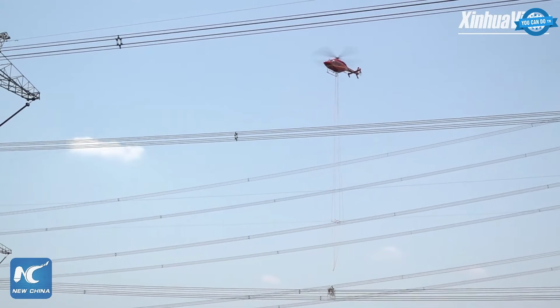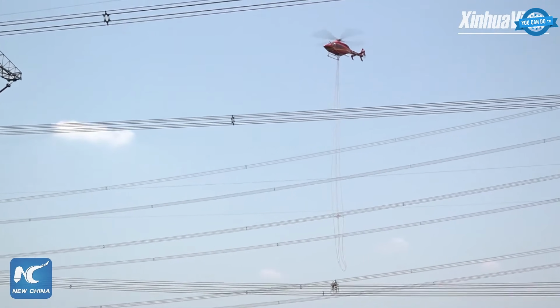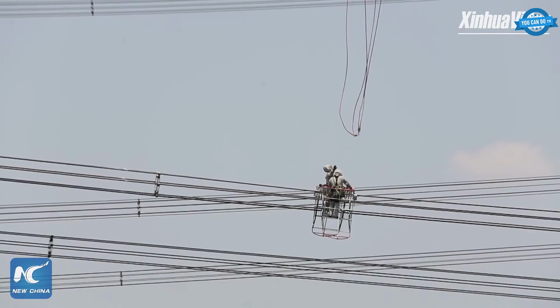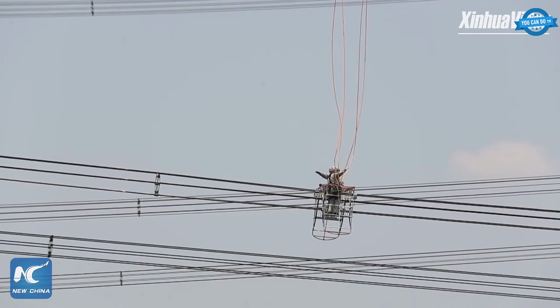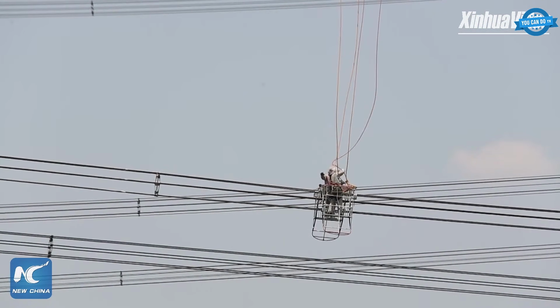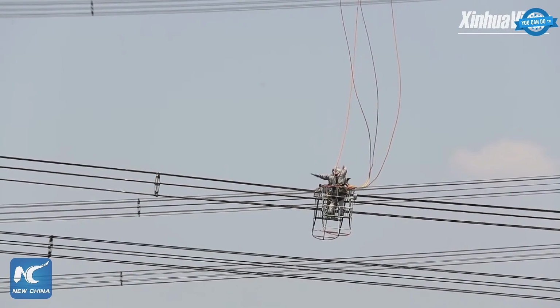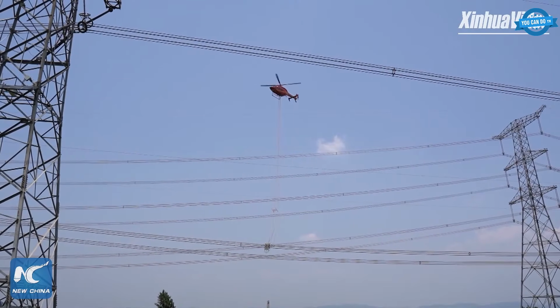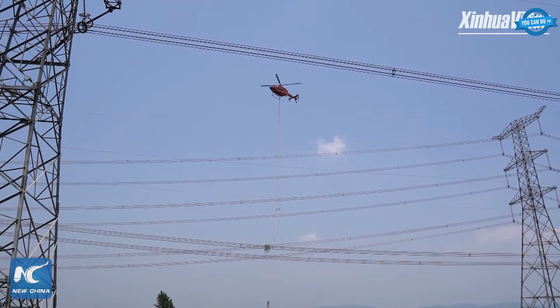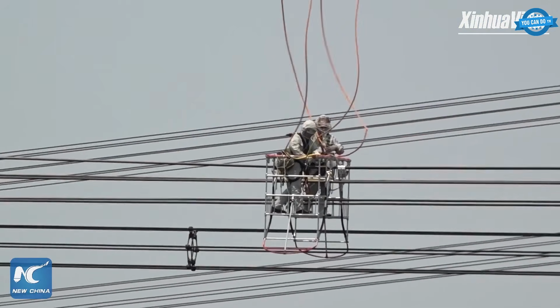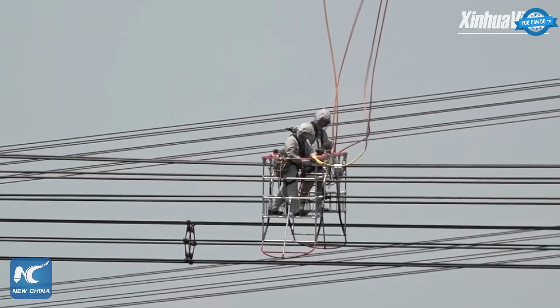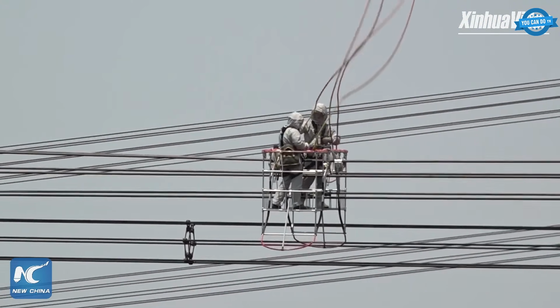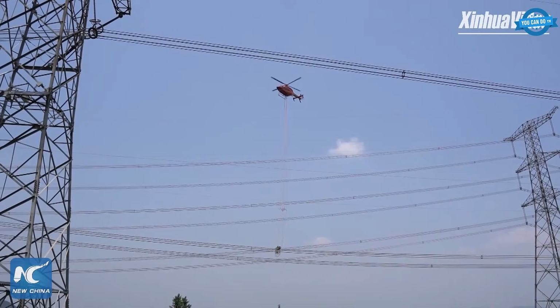Live-line helicopter maintenance is how damaged spacer bars get replaced without dropping the line. Linemen ride in a basket suspended 40 meters below the helicopter on insulating rope. The instant the basket contacts the conductor, a strong recoil kicks back. Workers have to predict and adjust posture immediately, or they cannot stand up at all.